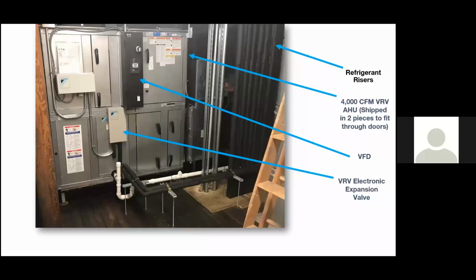On the right there, you can see those refrigerant risers that I touched on, and you can see the insulation on those as well. I believe this was on one of the upper floors, showing all the pipes feeding the units below. But as you can see, the shaft space required is still pretty small with these pipes. And then also there's that small white PVC piping, which is for the condensate dripping off that coil when it's operating and cooling.